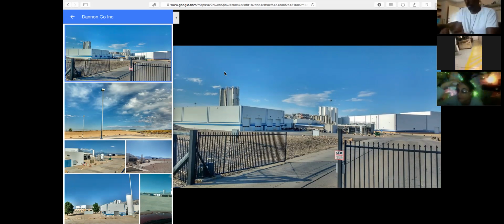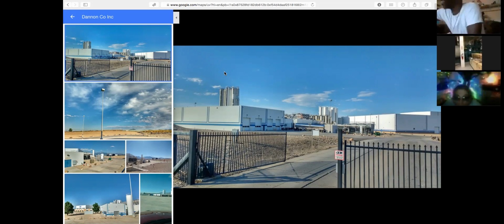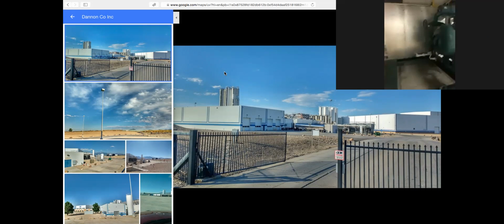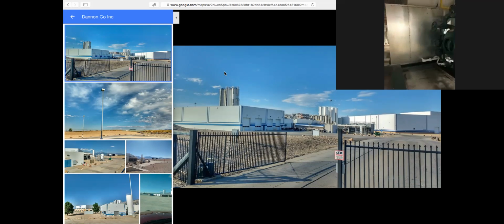Found a way to flip the screen around so you don't have to see my ugly mug. Okay, in here is this. Let me back up so you can get a bigger picture of it. Here's that ammonia compressor, the heat pipe right there at the fans. It's probably about 10 feet tall, with a 500 horsepower motor. There's the ammonia compressor. You can see the ice building up on top of it. There's that big tank, about 8 or 9 feet long. And right behind it, inside this insulation, is the heat exchanger where the glycol and the ammonia exchange the heat.